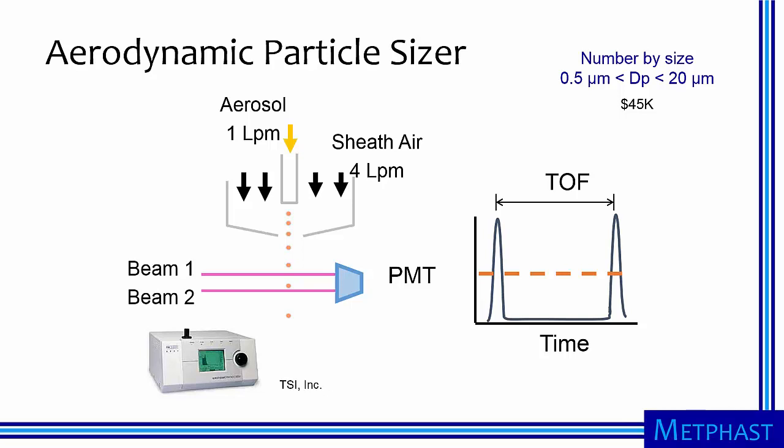The time that it takes to traverse the two beams is called the time of flight. Small particles, roughly less than 500 nanometers, accelerate rapidly to the same speed as the air in the nozzle. The inertial properties of larger particles causes them to increasingly deviate from the air flow velocity and have longer and longer times of flight. In this way, particles can be counted and sized at the same time.